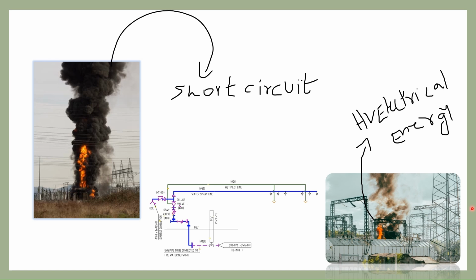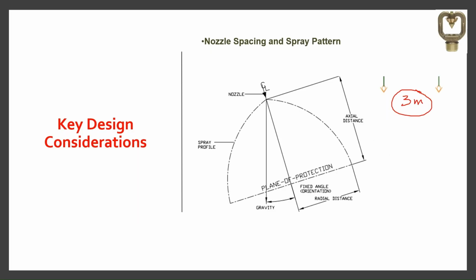That's why water spray systems will be designed in accordance with NFPA 15. And also, the main purpose of water spray system is not only to put out the fire, but to cool all the surfaces to stop the fire from restarting after the system is turned off. Since our topic is related to the water spray system design basics, we need to talk about the critical design considerations that we need to keep in mind when setting up a water spray system. So nozzle spacing and spray pattern.